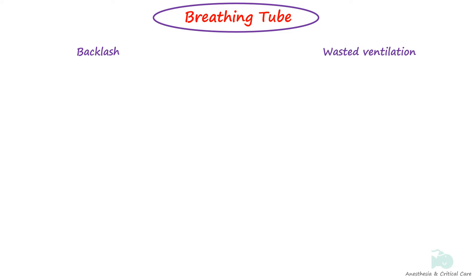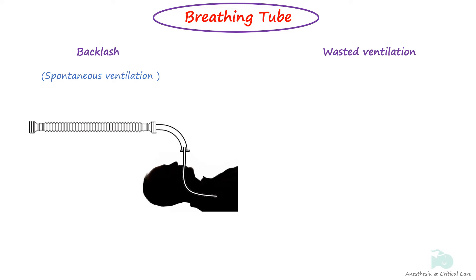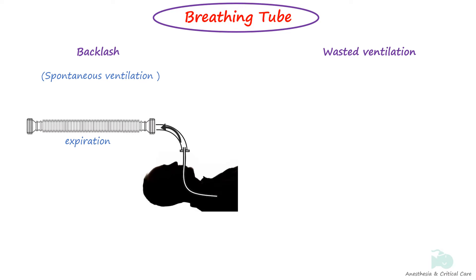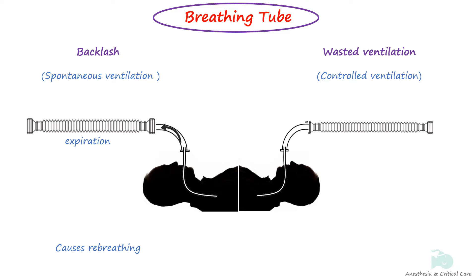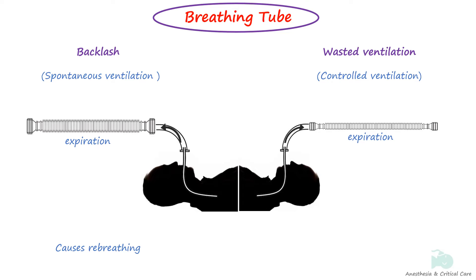Because the breathing tubes are distensible, two important phenomena occur when using them: backlash and wasted ventilation. Backlash is seen during spontaneous breathing where breathing tubes tend to collapse during inspiration and bulge during expiration, which may cause re-breathing. Wasted ventilation is seen during controlled breathing — the tubes tend to bulge on positive pressure breath (inspiration) and return to resting position on exhalation, resulting in less volume entering the patient than the one leaving the reservoir bag or ventilator.